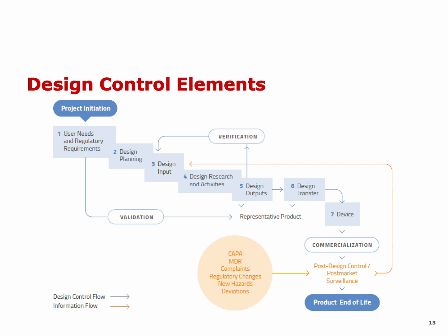This is where, when we look into post-design control and post-market surveillance, we always talk about the following procedures. These are SOPs that we need to have in place. These are teams that we need to have in place in our medical device manufacturing facilities or companies. One of them is CAPA, which is the corrective action and preventive action. This is where we need to have a quality assurance system in place where we can collect the complaints.